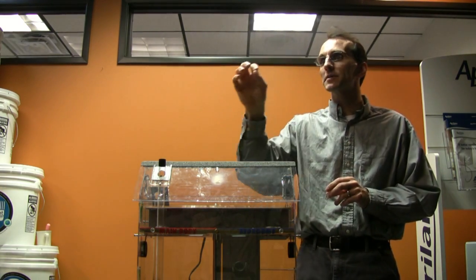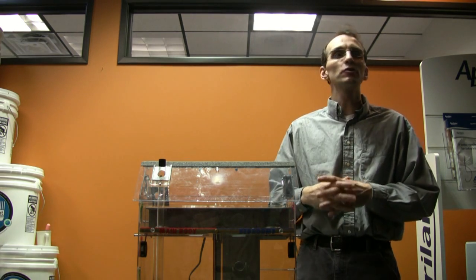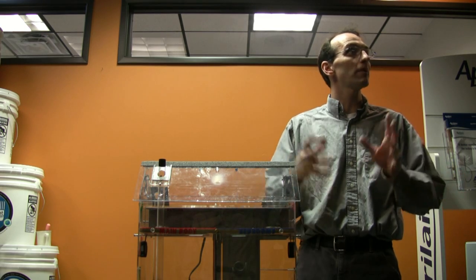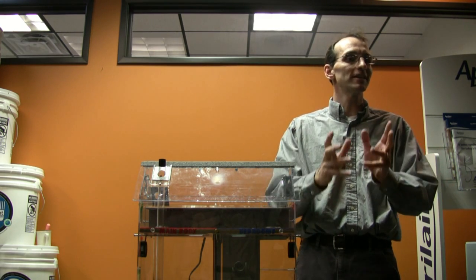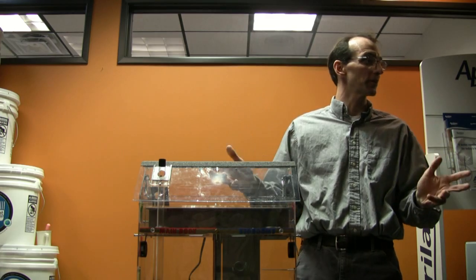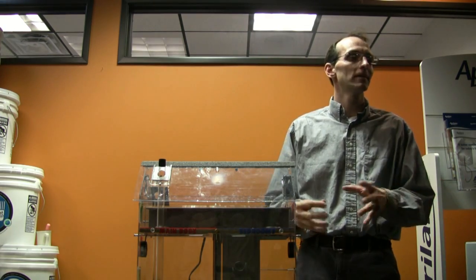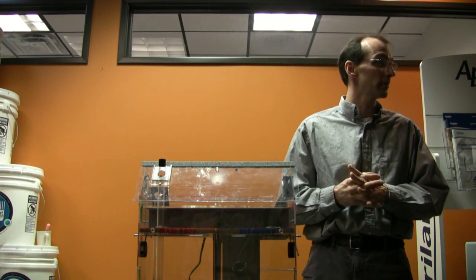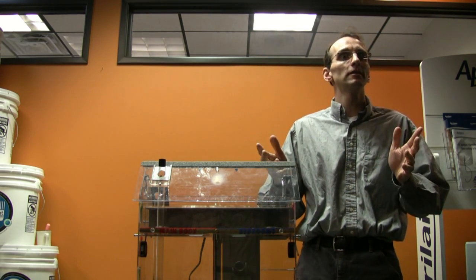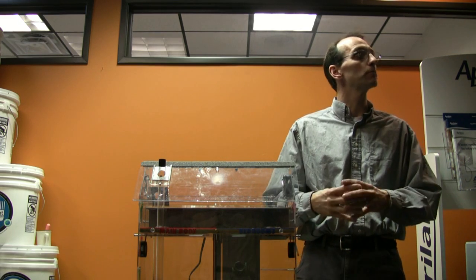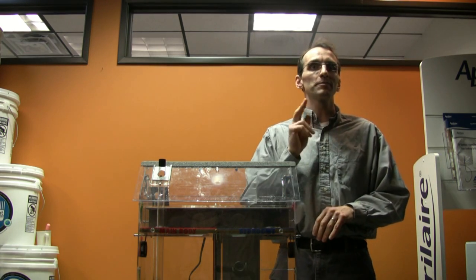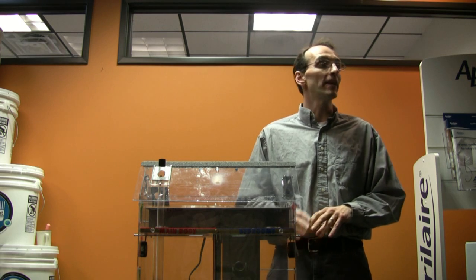When you see the little white deposits around the top of your water heater, those are created by spillage. That's exhaust gases. It's mineral deposits and rust taking place because your exhaust didn't actually make it out of the building when the water heater started up. It's spilling back into the room. Also, all the carbon monoxide is spilling back into the room. And when you have an abandoned water heater like I'm talking about, it's going to spill for a lot longer because the flue is improperly sized now. Knowledgeable heating contractors know that they are supposed to change the flue, and they will point that out to the homeowner.